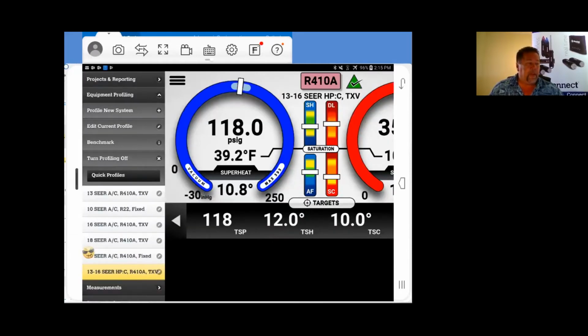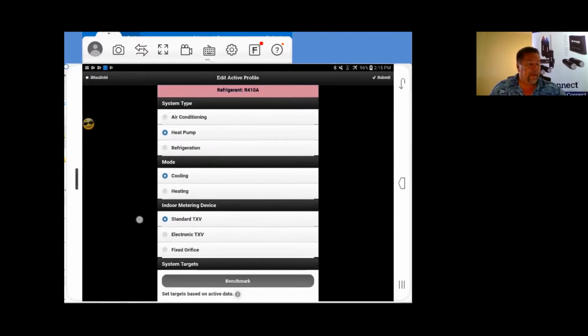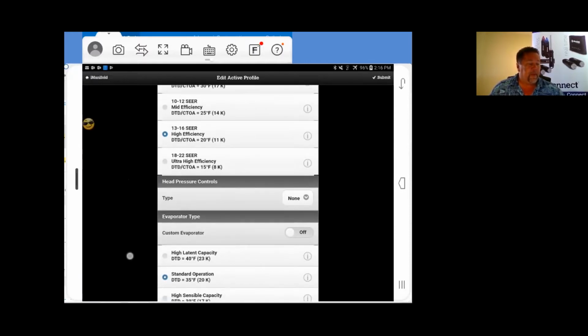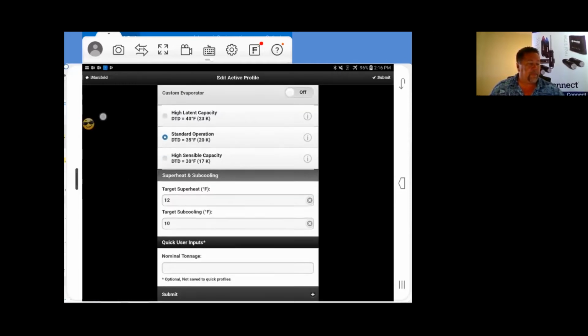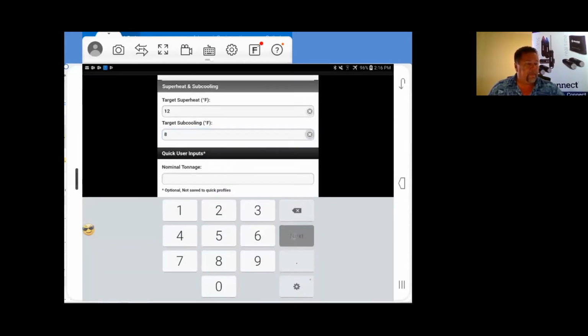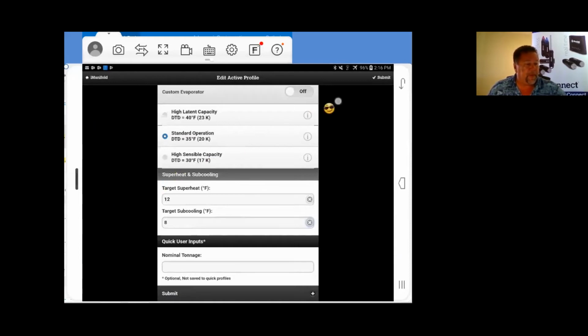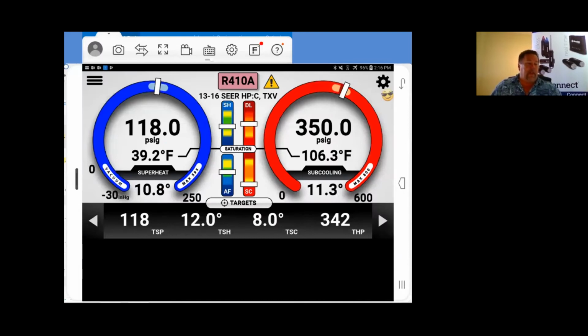our bar menu, and we'd go up here to edit the current profile. Tap edit current profile, scroll down to our target data, and as you can see on our target subcooling, we need to put an 8 in there. We put the 8 in, and we go up here to our best friend up here again, submit. We tap submit. There's our subcooling target. That is adjustable. And now, as you can see, our subcooling is high again. So this will show you exactly what's going on as far as the system goes. Now, remember this, you can also use as little or as much of the system as you want.